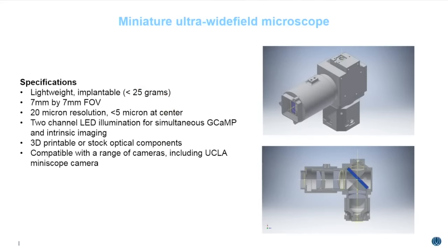This is a lightweight, implantable single-photon microscope. It offers a 7×7 mm field of view; at the perimeter you have 20 micron resolution, and at the center close to single-micron resolution — roughly less than 5 microns. It has a two-channel stimulation system so you can simultaneously record GCaMP and intrinsic signals. It's made from 3D-printed material or stock optical components, can be fabricated for less than a thousand dollars, takes three hours to build, and is compatible with a wide range of cameras including the UCLA miniscope camera.